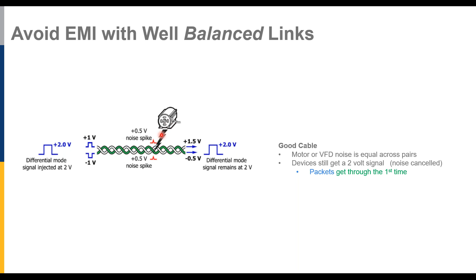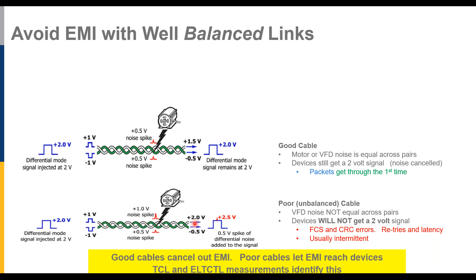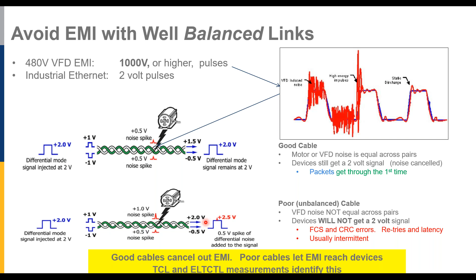Now, if our cable is not well balanced, that common mode noise that is induced onto the cable may not be received equally by each leg of the pair, and we fail to maintain our 2-volt differential, which causes our problem. There's a view of it on one of our trusty oscilloscopes. So how do I make sure that my cabling is well balanced? Well, there's a parameter called transverse conversion loss, or TCL. The definition: we send a differential mode signal down the cable and listen for common mode signal coming back. Most of the noise that's induced on the cable is common mode, and we can ignore that, but if it converts to differential mode, that's where it may cause the corruption. So the important thing to remember about TCL is that it makes sure our cabling has immunity to this interference.